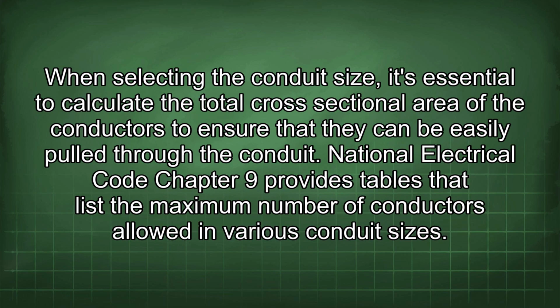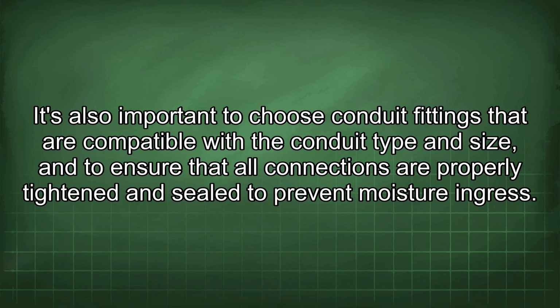When selecting the conduit size, it's essential to calculate the total cross-sectional area of the conductors to ensure that they can be easily pulled through the conduit. National Electrical Code Chapter 9 provides tables that list the maximum number of conductors allowed in various conduit sizes. It's also important to choose conduit fittings that are compatible with the conduit type and size, and to ensure that all connections are properly tightened and sealed to prevent moisture ingress.